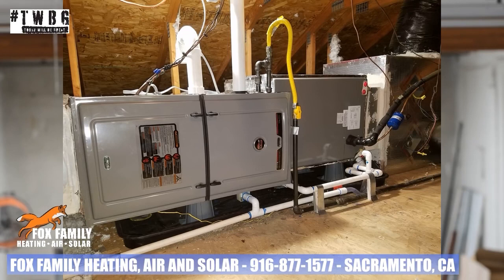We always try to offer a condensate safety switch to protect your home from potential damage. The secondary drain pan under the evaporator coil in the attic is a potential source of problems too. So we like to make sure that it's ready for any emergency by making sure there's no insulation in the pan and that all water that might get into that pan will flow out correctly.